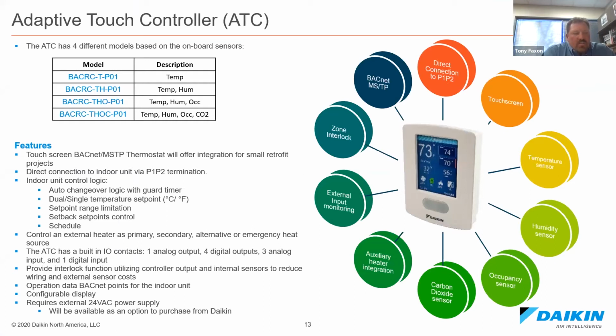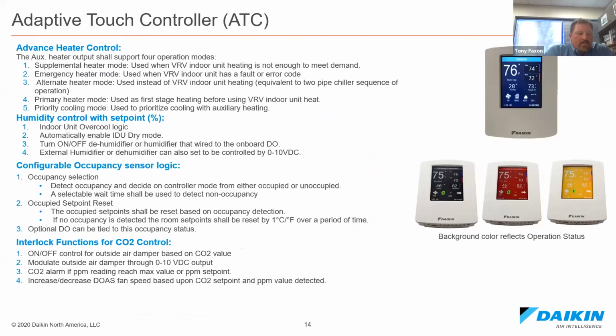This controller can run auxiliary heat as primary, as secondary, as alternative, or emergency. It also has built-in I/O contacts that allow for controlling alternate equipment, such as using its CO2 sensor to control a fresh air intake system that brings more air through the ductwork if high CO2 levels rise. You could use its humidity sensor to control a humidifier or other like type systems. The Adaptive Touch Controller has direct BACnet capability.